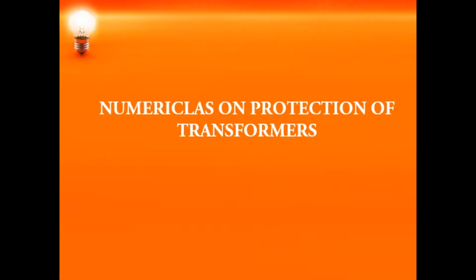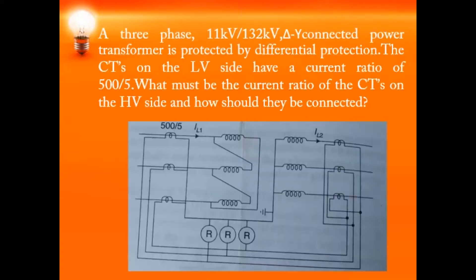Welcome everyone. In this session let us solve the numericals on protection of transformers. The first one is a three-phase 11 kV / 132 kV delta-star connected power transformer protected by differential protection.